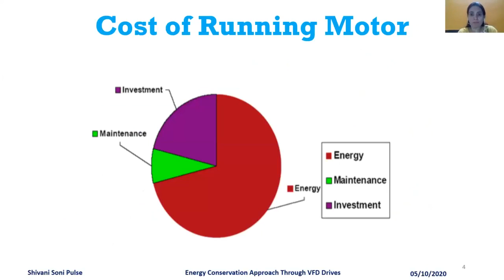You might be aware of the term VFD. VFD is the variable frequency drive. It is also known as the AC drive or adjustable frequency drive. The working principle of the VFD is that you can control the speed with the help of the frequency. The synchronous speed of the motor is directly proportional to the frequency applied to the motor, and it also depends on the poles of the motor.